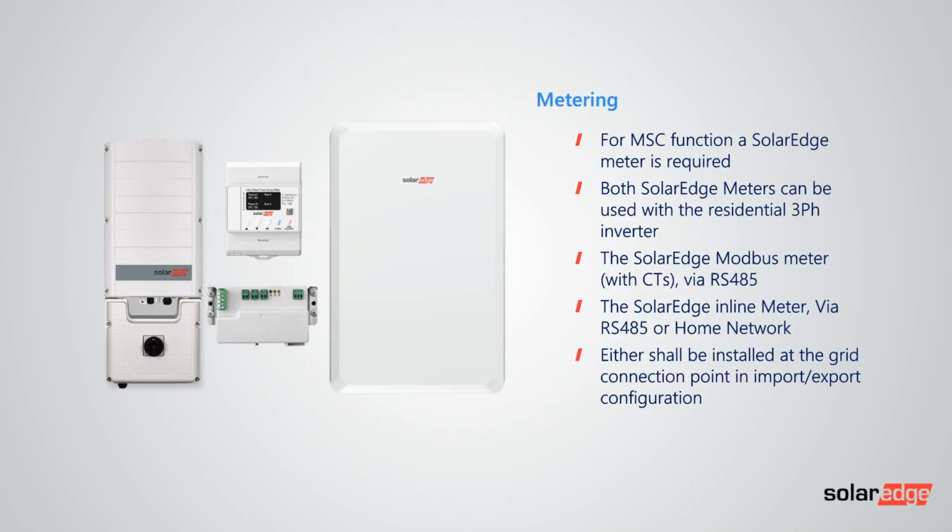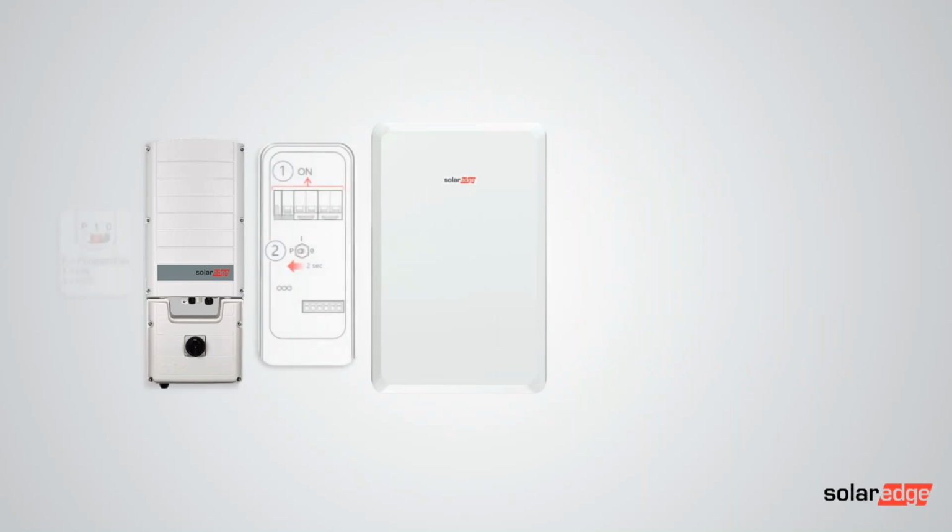Because there's a battery, now having a meter also becomes mandatory, because the inverter needs to be set up in MSC function, so maximizing self-consumption. The meter obviously needs to go in the main switchboard. You can wire the Modbus meter RS485 or the inline meter RS485, or that can also communicate over Home Network. And when it's all commissioned, just make sure it's obviously in import-export configuration.